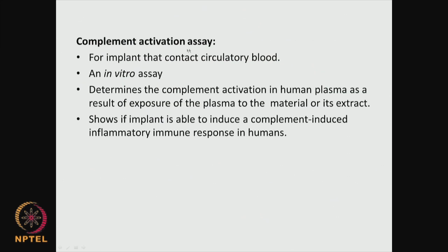Then there are assays for complement activation. Again, as I said, the complement activation with respect to the circulatory blood. This is also an in vitro assay. It determines the complement activation in human plasma as a result of exposure of the plasma to the material. This assay is very useful, it tells you whether the complements will get activated.